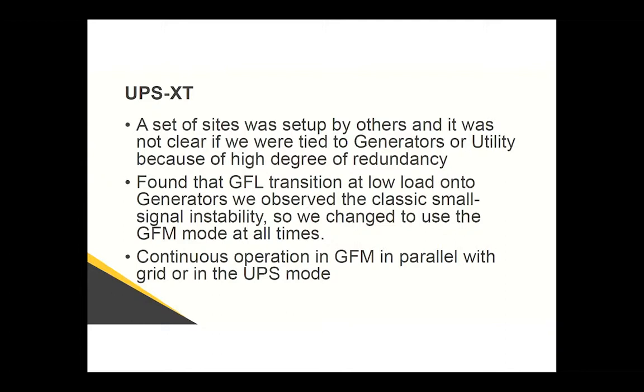So usually we knew whether we were transferring to a diesel generator or to a utility, but then we got to a site where it was so redundant that they could put the diesel generator either on our input or our output and didn't really have a way to tell us if we were connecting back to the utility or to a diesel generator. So what we found was when we transferred back to the utility as a grid following inverter, when we were lightly loaded, we had a small signal instability. So we changed that to use grid forming, got rid of that problem, and that's how we left the system. So we've got continuous operation in grid forming mode now with those fairly large systems.